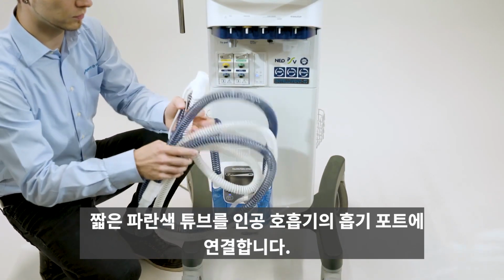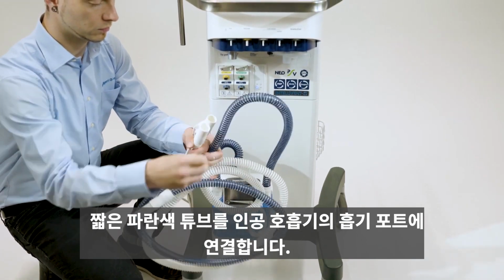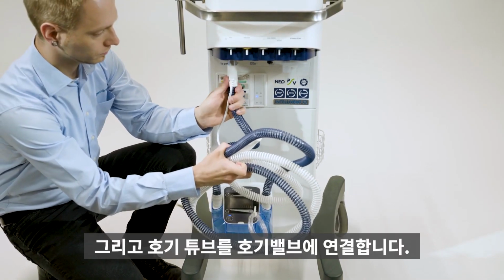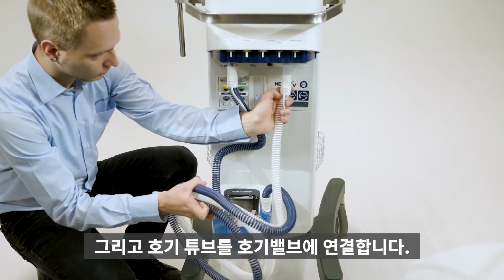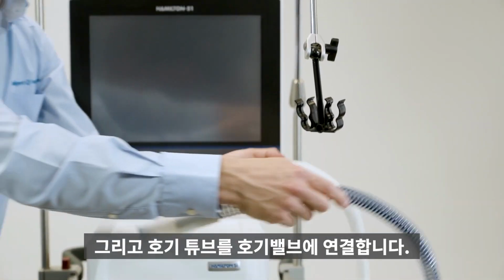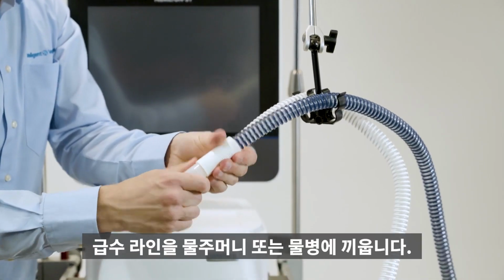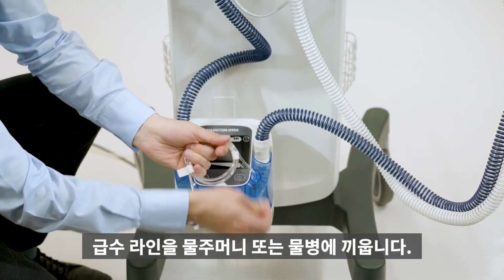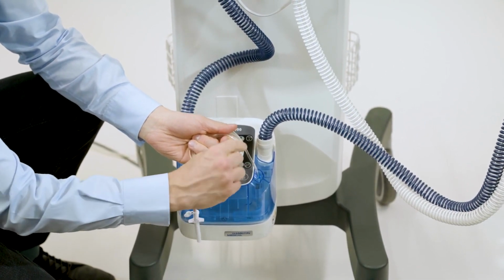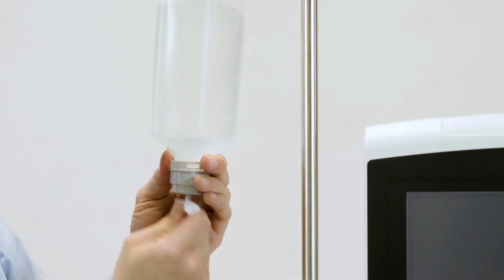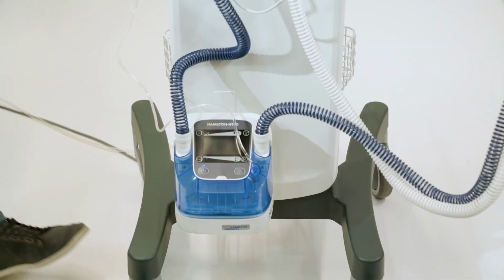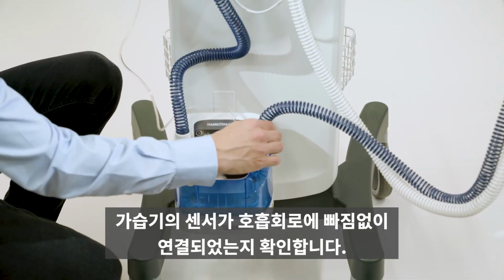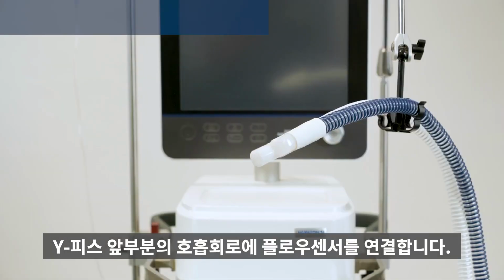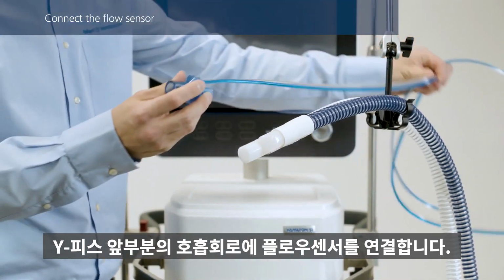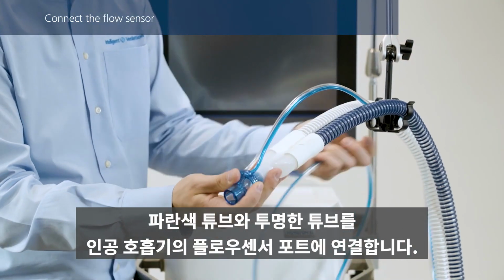Connect the shorter blue tube to the inspiratory port on the ventilator. And then connect the expiratory tube to the expiratory valve. Insert the water feed line into the water bag or bottle. Make sure that all electrical contacts on the breathing circuit match the connecting element on the humidifier. Insert a flow sensor into the breathing circuit in front of the patient connection, that is, the Y-piece.